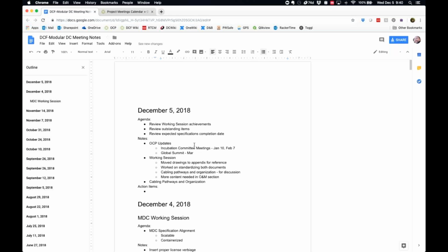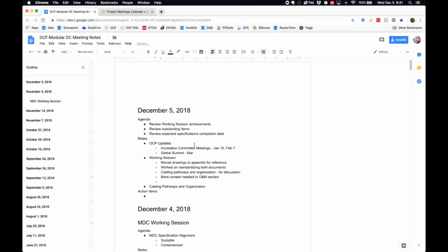But as we're talking about the cable and pathways, and I'm thinking about specifications, we have a lot of the specifications of the physicality of the module: the strength, the IP rating, the paint coating, the floor loading, and all that stuff. But do we even have, for example, the aisle width should be this wide, so that inside the IT space you should be able to roll this size rack into it? When I thought of the cabling pathways, I wondered whether we are missing a few other comments that we might need inside the white space, and maybe we categorize those together.